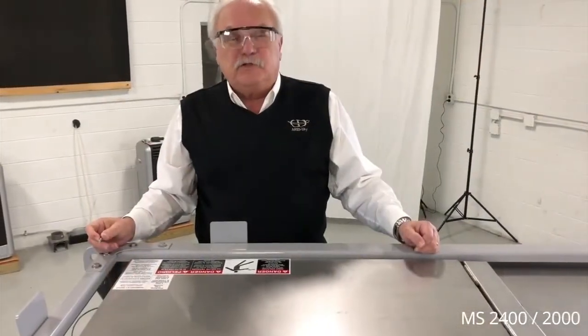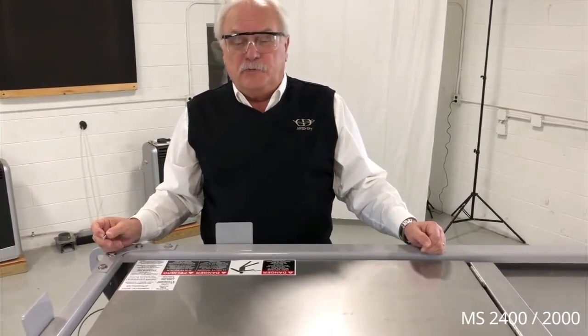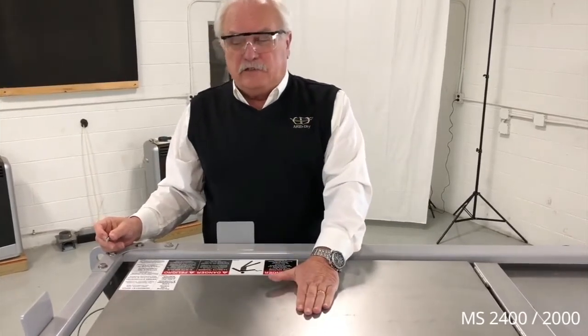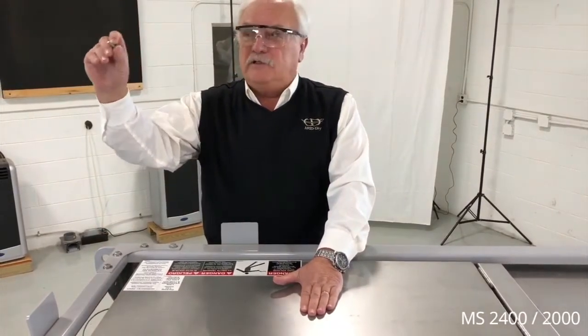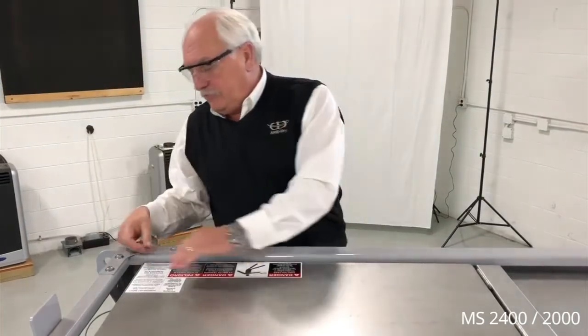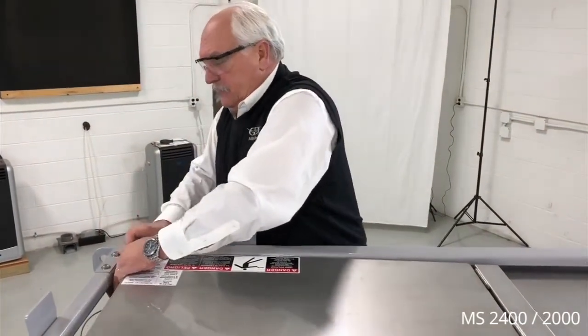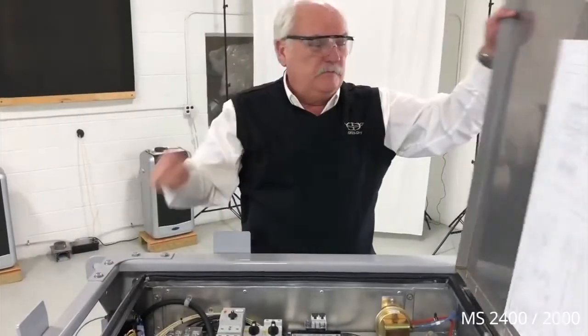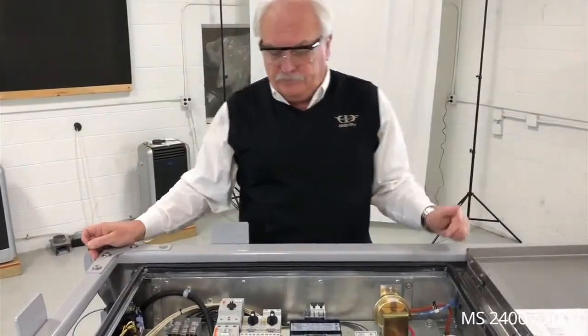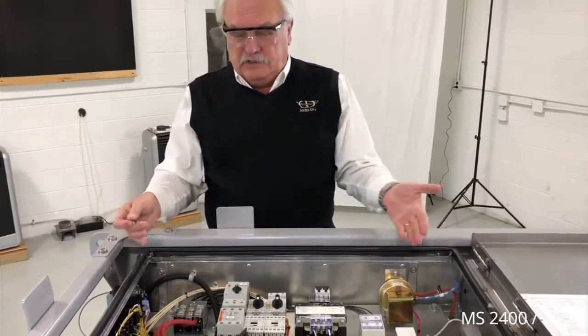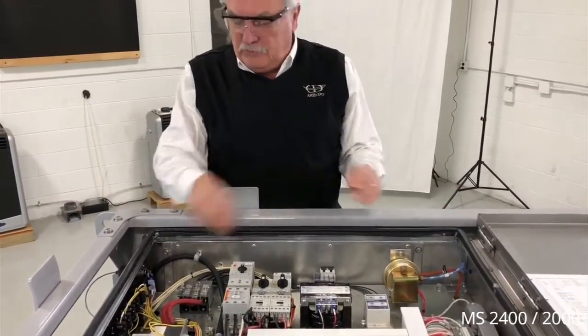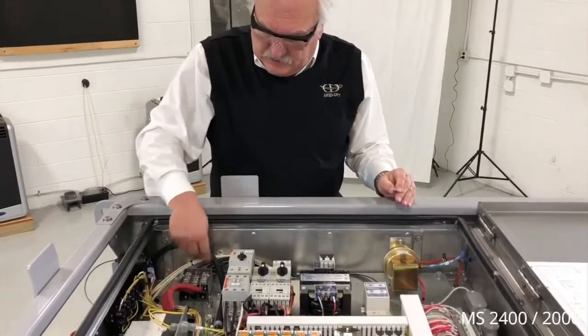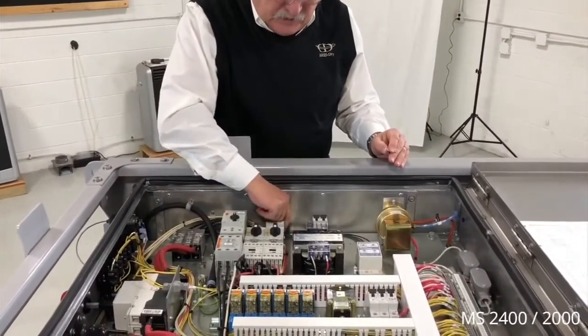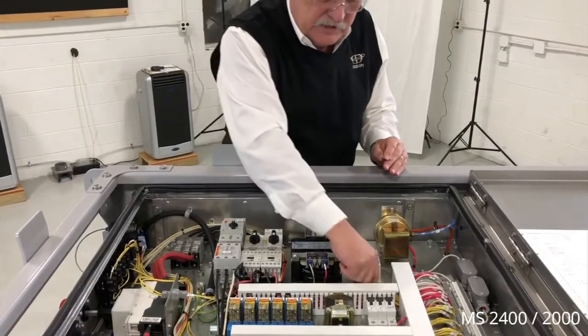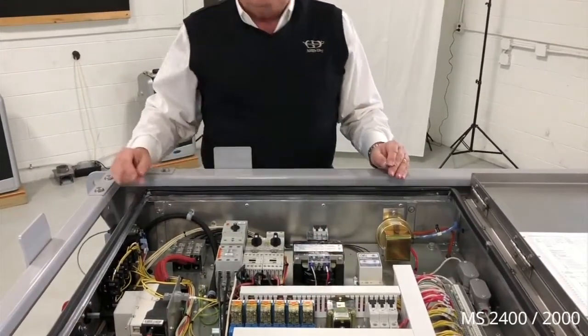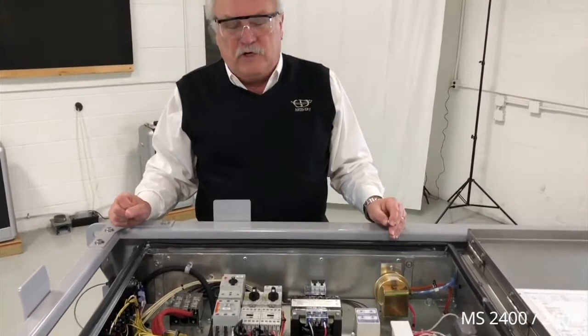The next step is to check the electrical connections in the control panel. The control panel is located on top of the unit, and you remove 2 7/16" bolts from the end, and then the panel can be lifted and opened. Inside the panel, you'll see the electrical components. You'll want to go through the components and make sure everything is tight to the touch. Screwdrivers are an essential part of this. You want to check everything in the panel and make sure all the wires are tight before any power is applied to the panel.